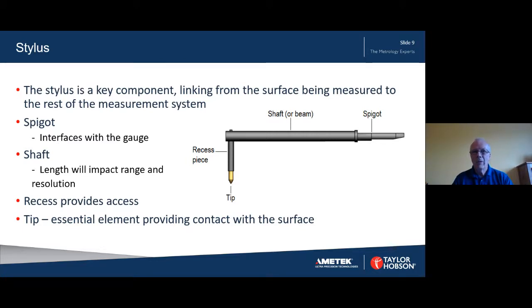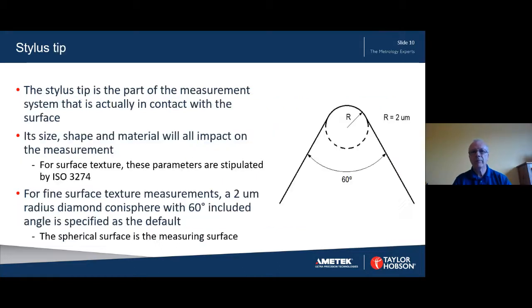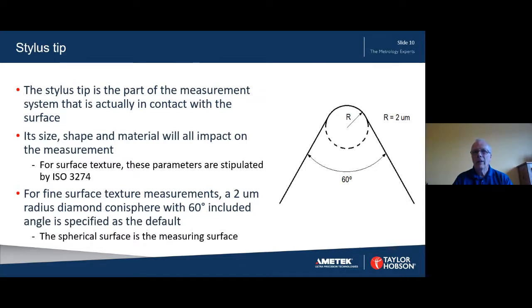The stylus tip is an essential element forming the contact with the surface under test. The size, shape, and material of the tip will all affect the results. For surface texture, these properties are stipulated in the relevant ISO standards. For fine surface finish, the default stylus is a 2 micron radius, 60 degree diamond conisphere. Other styli are permitted; for example, a 90 degree stylus angle is very common. Stylus radii of 5 micron and 10 micron are also common depending on the roughness values being measured and the industry practice. In many situations the impact on parameter values due to changing the stylus size will be very small.